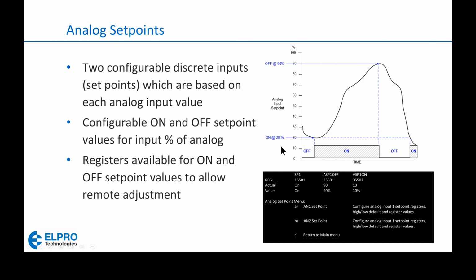So what that radio does is, the radio that has the 4 to 20 milliamp signal wired into it then radios that set point value to a remote radio system that triggers a digital output. That digital output could then be wired to a pump, and that pump could then be filling this water storage tank, for example. So the set point will turn on at your minimum value, whatever you set it to, and then it'll turn off at your maximum value, again, whatever you decide to set this to. So it's designed for filling a tank or filling a liquid storage tank.